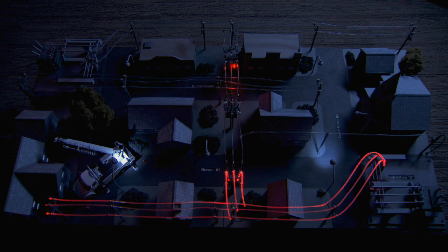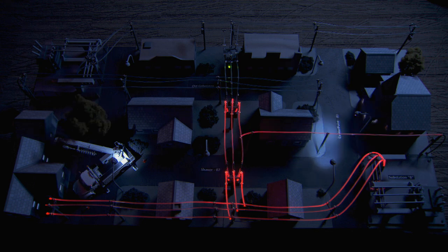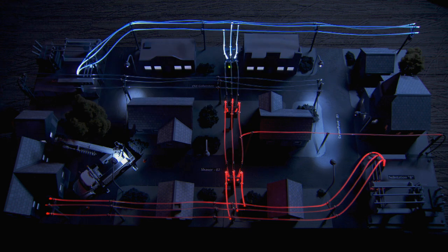The next step is to locate where the fault occurred. With the help of smart meters and intelligent grid switches, we can isolate the problem on the circuit. We open the middle and far switches so that the lines are now safe for our crew to begin work. By isolating the problem with intelligent grid switches, our crew spends less time searching for the source of the fault manually. The intelligent grid will let us begin to restore power to as many people as possible as soon as possible. The sensors recognize that the fault is on the middle row of power lines, not the far row. The fault has been isolated to the middle row so that the breaker at substation A can be automatically reset. Electricity is brought back to the farthest row of houses even before the crew arrives — power is restored to these folks in minutes or seconds, rather than the hours it might take today.